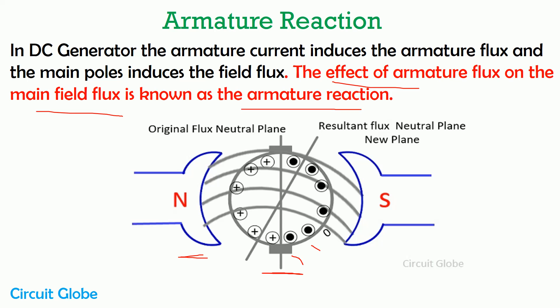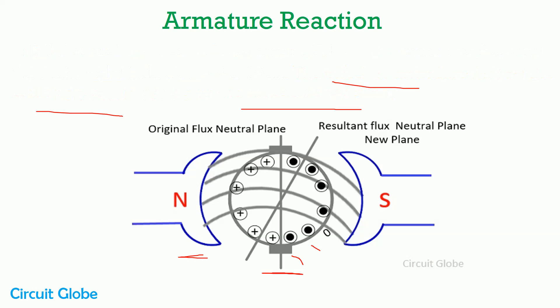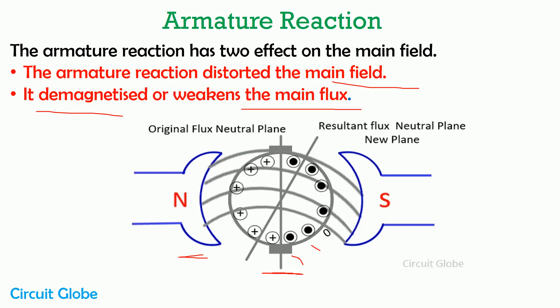The armature reaction has generally two effects on the main field flux. The first one is that the armature reaction distorts the main field, and the second one is that it demagnetizes the main field flux. If armature reaction distorts the main field, that means the total voltage generated in the DC generator will have its magnitude reduced. So we can say that armature reaction reduces the generated voltage of the DC generator.